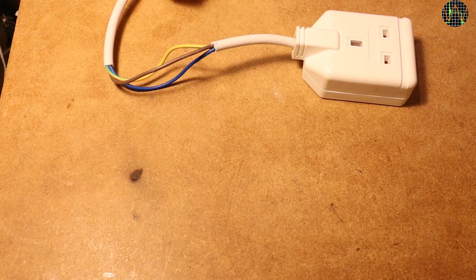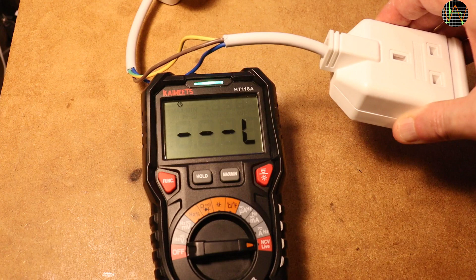Let's have a look at the NCV or non-contact voltage mode. It has two ways of operating. First, I'm using the antenna at the top in this setup using mains voltage. If I bring the blue neutral wire close to the antenna, the HT118A shows L for low, a green light, and beeps slowly. If I use the brown live wire, it shows H for high, changes to the red light and beeps faster. The function key switches to the live test, which, as you can see, demands a single lead.